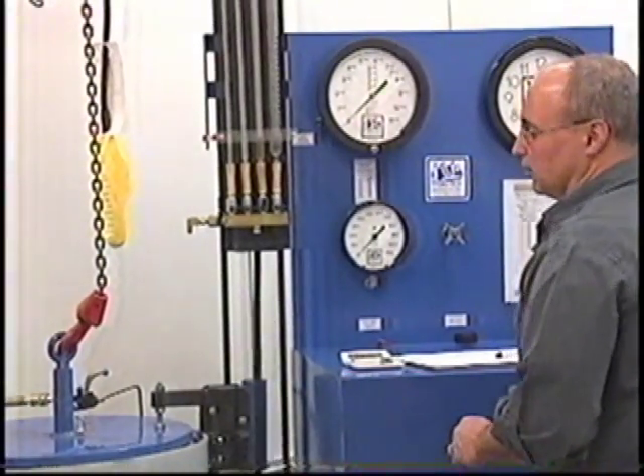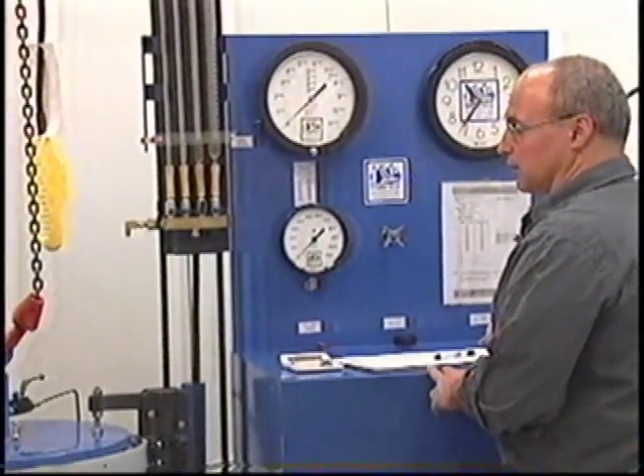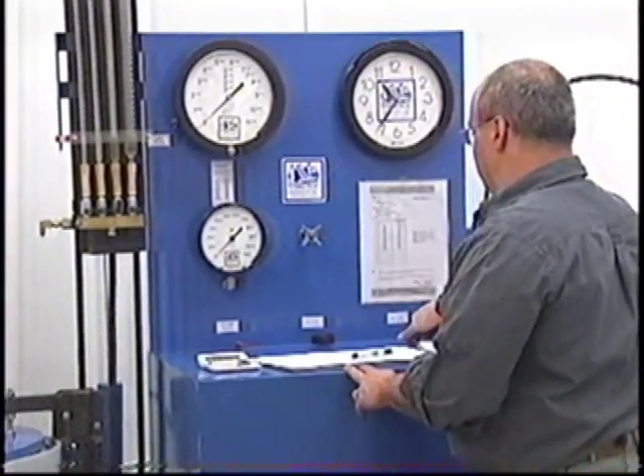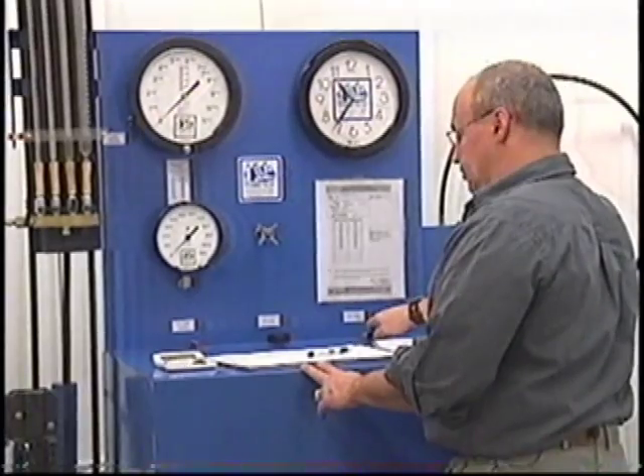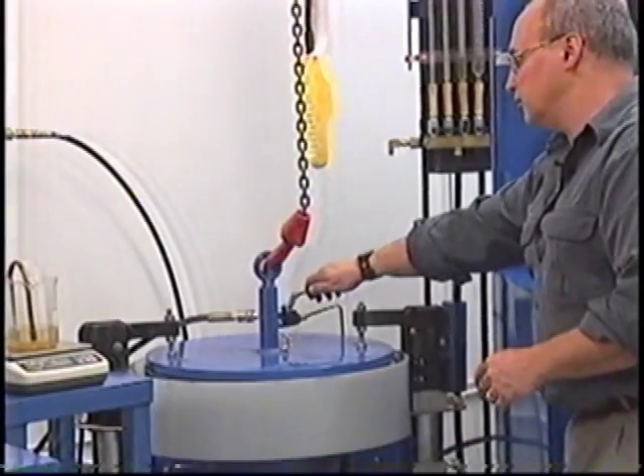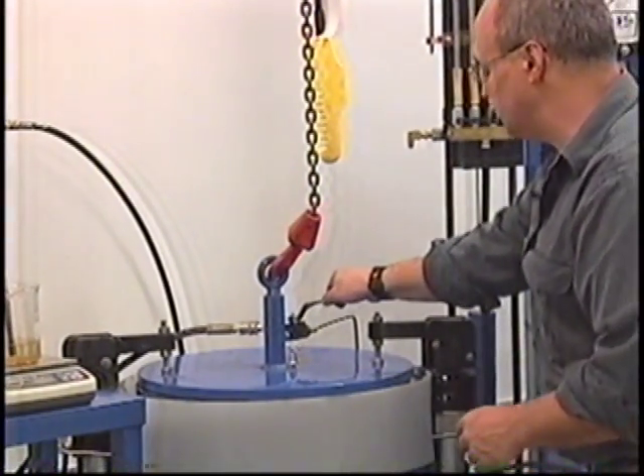Then we are also going to make sure that although the cylinder has been prefilled with water, it is important to make sure that all the air is out of that cylinder. So we are going to turn on the valve water to pump in cylinder. When a stream of water comes out of the high pressure bleed valve, we then shut that bleed valve off.